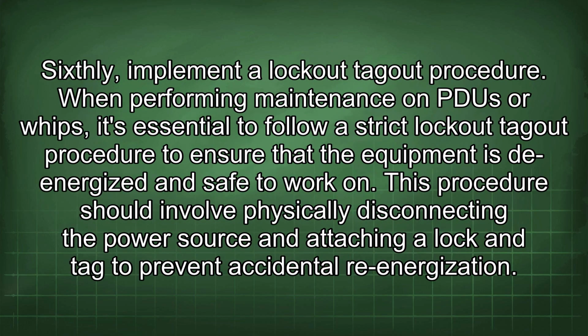Sixthly, implement a lockout-tagout procedure. When performing maintenance on PDU or whips, it's essential to follow a strict lockout-tagout procedure to ensure that the equipment is de-energized and safe to work on. This procedure should involve physically disconnecting the power source and attaching a lock and tag to prevent accidental re-energization.